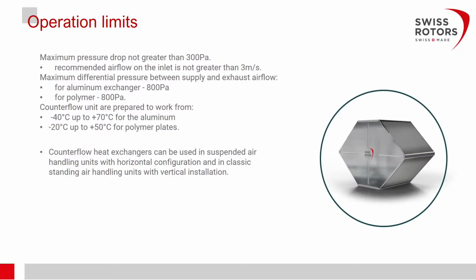And the maximum differential pressure for the aluminum plate exchanger is 800 pascals, and the same for polymer. And the temperature limit is from minus 40 degrees up to plus 70 degrees for the aluminum plates, and minus 20 to plus 50 degrees for polymer plates.